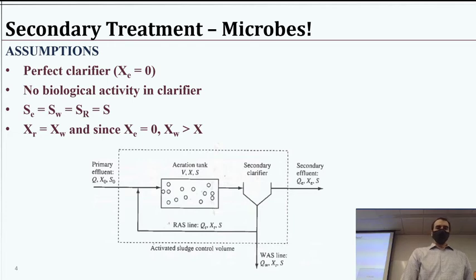Okay, so a few assumptions, and I've already touched on some of this. When we're dealing with these clarifiers, we first of all assume this XE is zero. That's right here. That's the perfect clarifier assumption. Another thing we go ahead and assume is that, you know, whatever's happening in this clarifier, there's not enough time or aeration or mixing or any of that to really have a significant amount of biological activity. So while we have water in here and there's a bunch of bacteria accumulating at the bottom, we're just not treating this as part of our treatment train in terms of looking at the reactions.